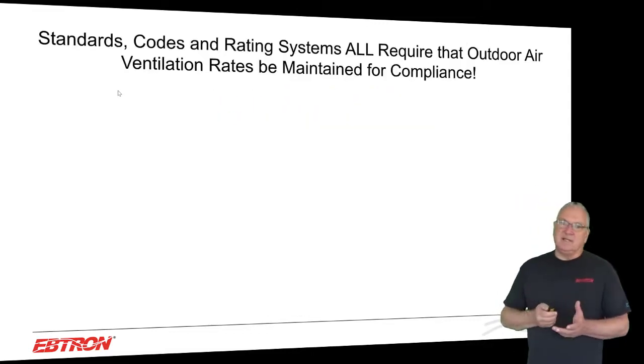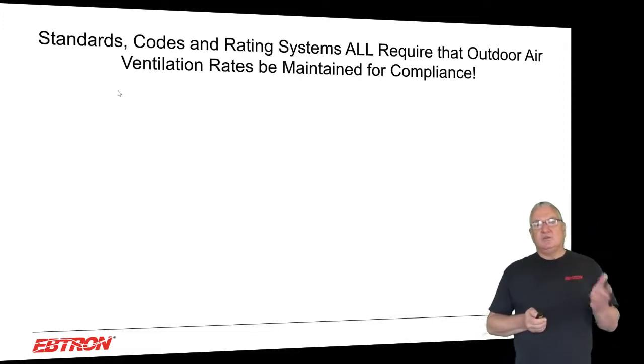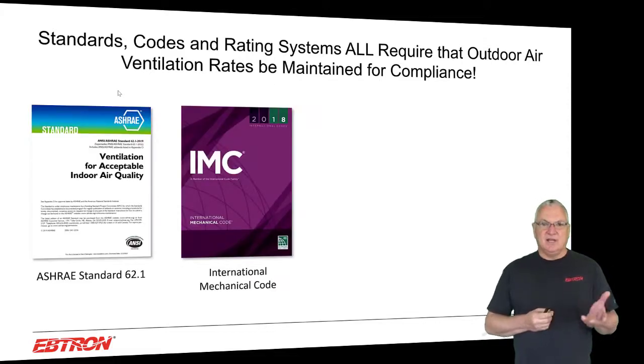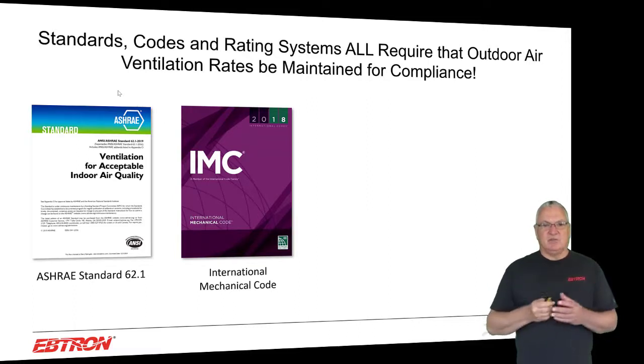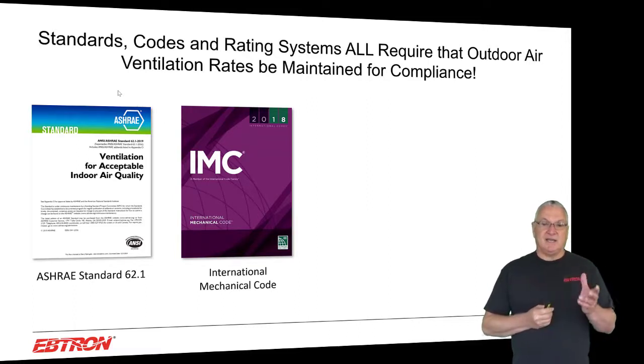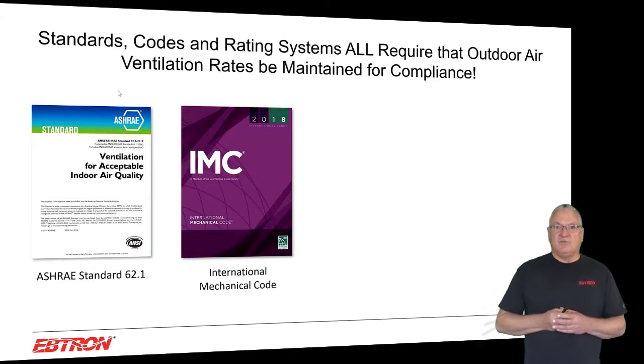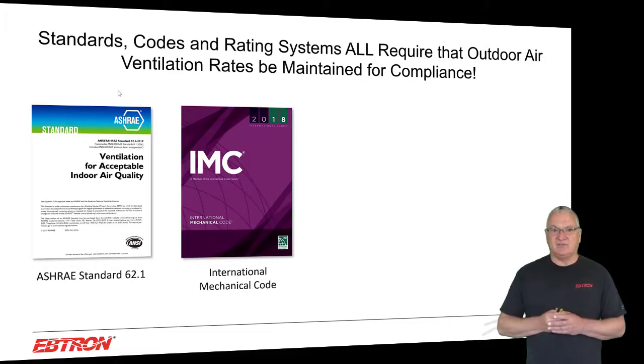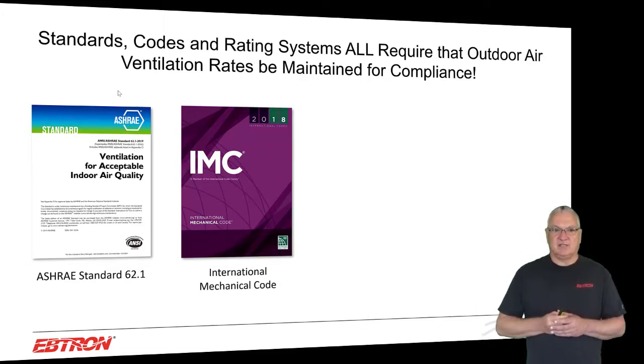When we talk about standards, codes, and rating systems, they all require that outdoor air ventilation rates be maintained for compliance. We have Standard 62, which is ventilation for acceptable indoor air quality — that's the one we really have to go by. And then the IMC, the International Mechanical Code, in one form or another has been adopted in most of the United States. When you look at the ventilation side of the IMC, it's really a strict interpretation of the ventilation rate procedure of Standard 62.